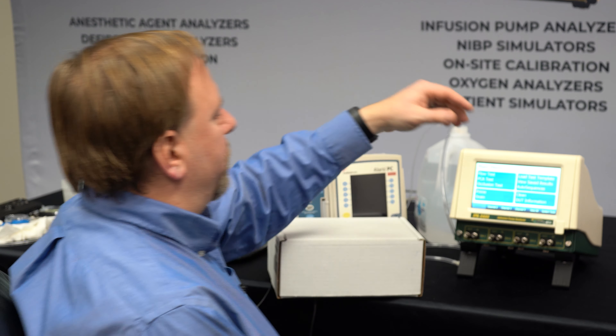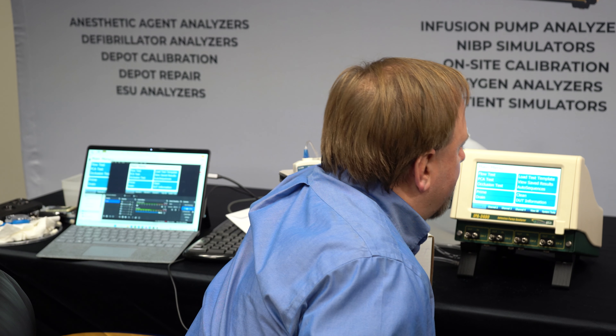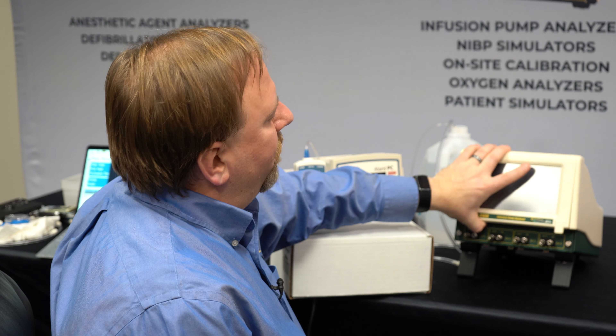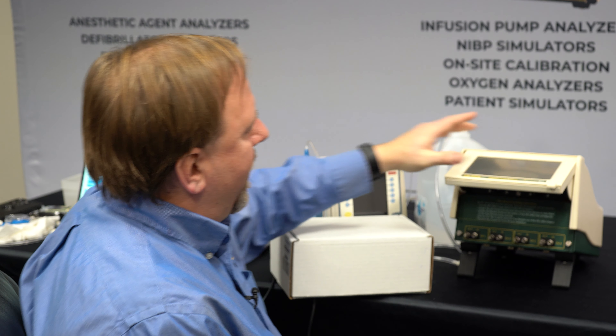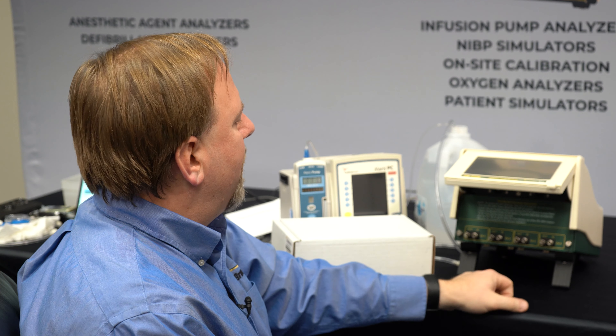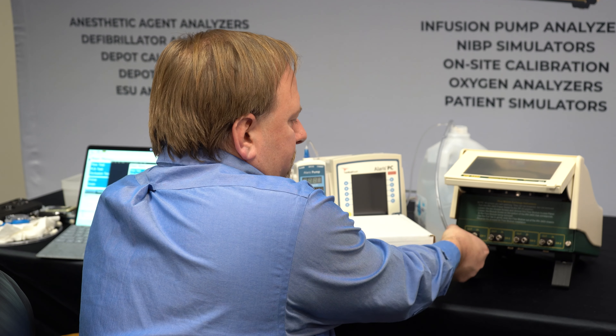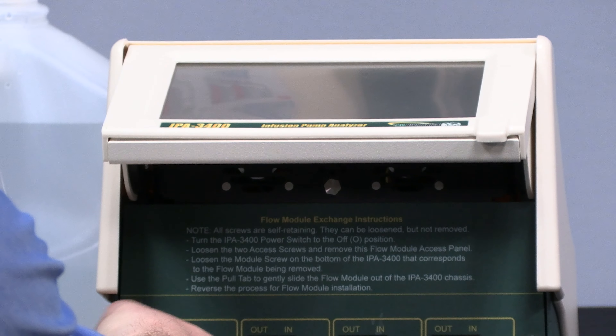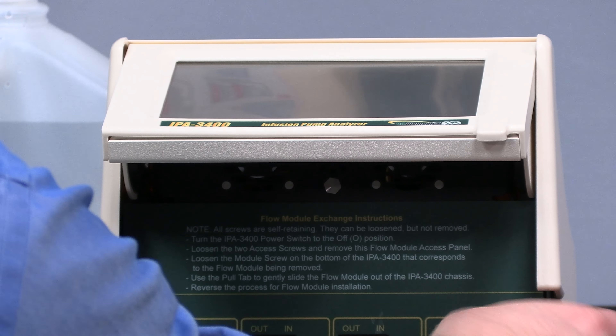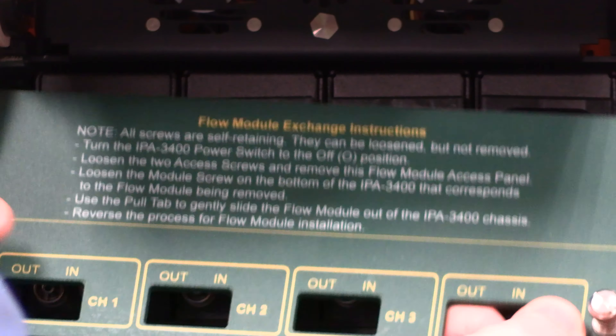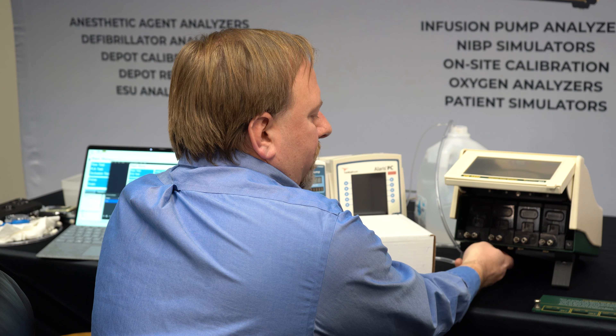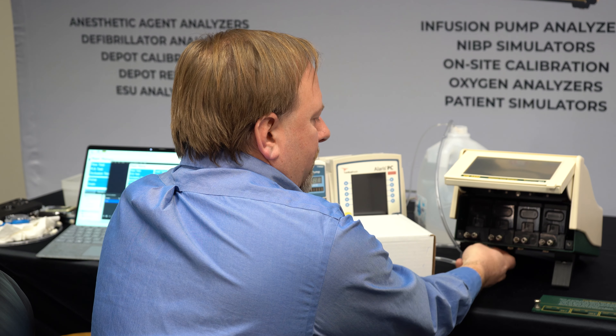We saw on the system info screen that one of our channels needed to be calibrated, so we're going to demonstrate how to get the module out and return it for service. The first thing we want to do is turn off the 3400. I'm going to hit the power switch in the back and we have to flip up the front panel. Once we do that, we have exposed our instructions for changing out the modules. We'll follow those instructions, which consist of removing these two thumb screws on the front panel.